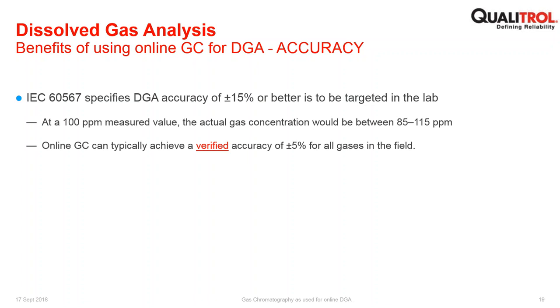IEEE IEC 60567 specifies that accuracy for DGA must be plus or minus 15% or better. So in reality, this would mean that a measured result, or an actual concentration, of 100 ppm might be reported anywhere between 85 and 115 ppm. And this is for laboratory conditions.